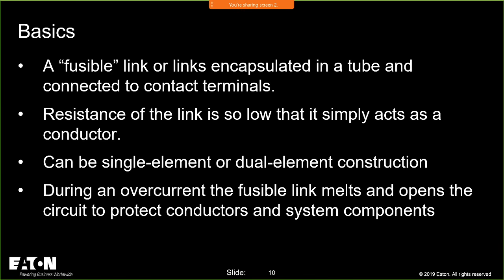Just like a circuit breaker or any type of device you put in the circuit, there will be a resistance and impedance to that. The elements and the contacts and whatnot. Breakers have contacts. Fuses will have the element, and you'll see both fuses and breakers, they'll be warm.